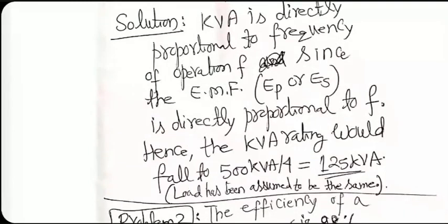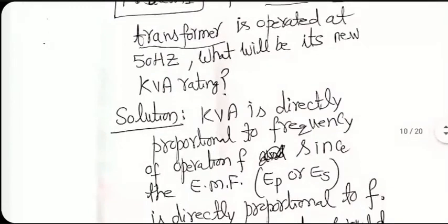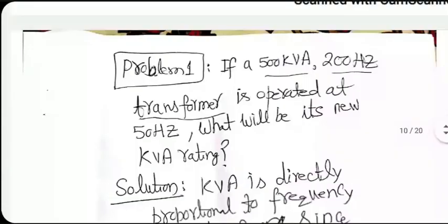The question can be twisted in the other direction also. Suppose this rating were at 50 hertz and then you operate the transformer at 200 hertz. What will happen? The rating should go up by a factor of 4, but you have to be careful whether the windings are sufficiently thick to handle that. That's the practical side of the story.